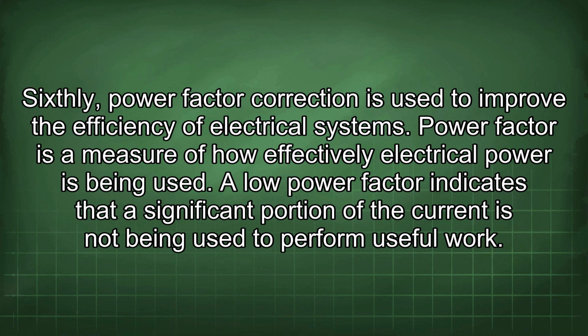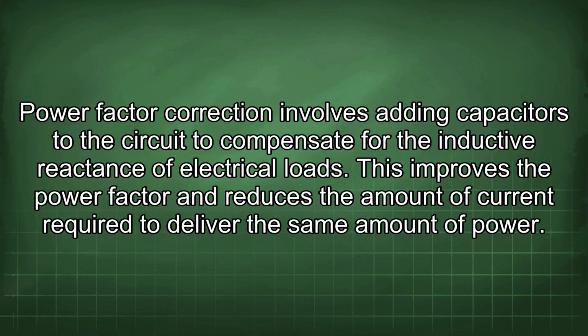Power factor is a measure of how effectively electrical power is being used. A low power factor indicates that a significant portion of the current is not being used to perform useful work. Power factor correction involves adding capacitors to the circuit to compensate for the inductive reactance of electrical loads. This improves the power factor and reduces the amount of current required to deliver the same amount of power.